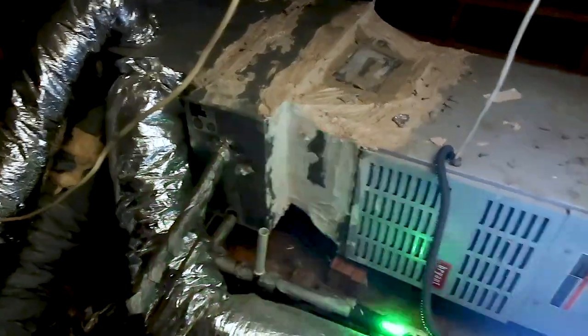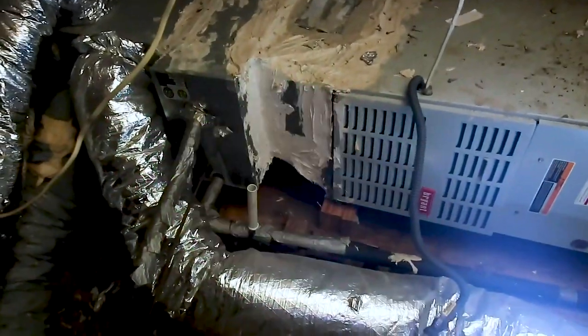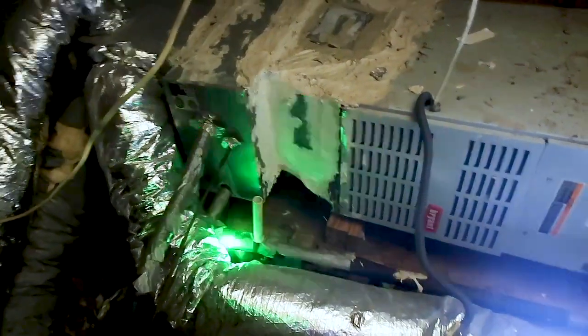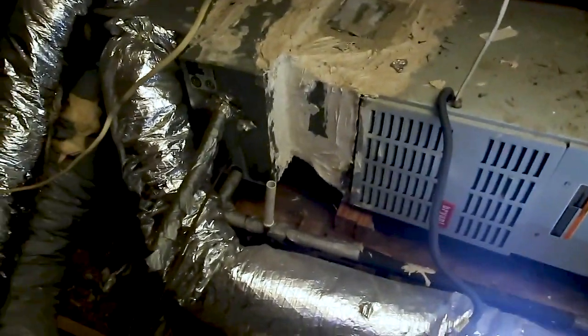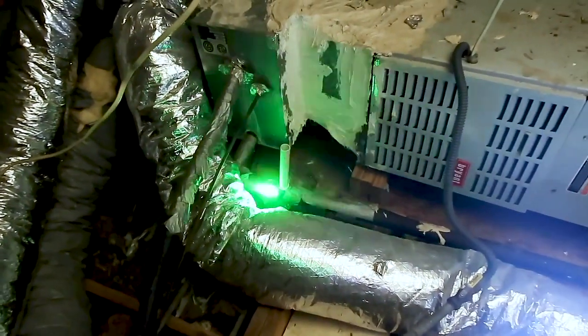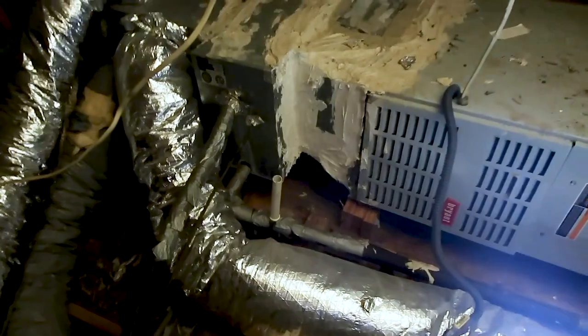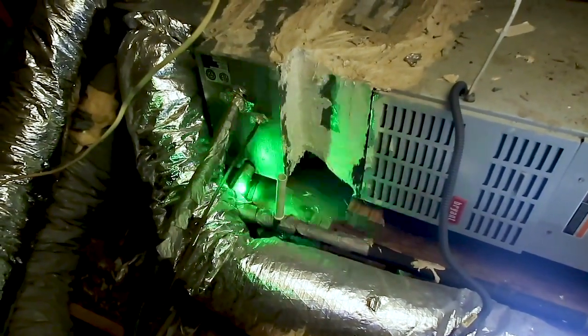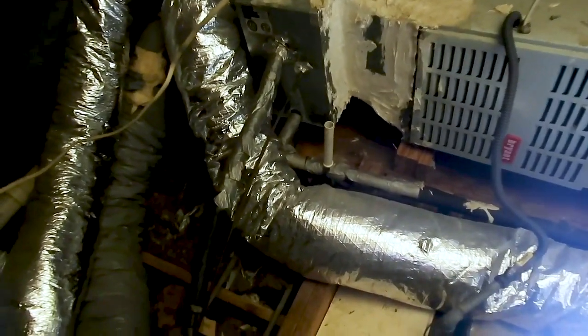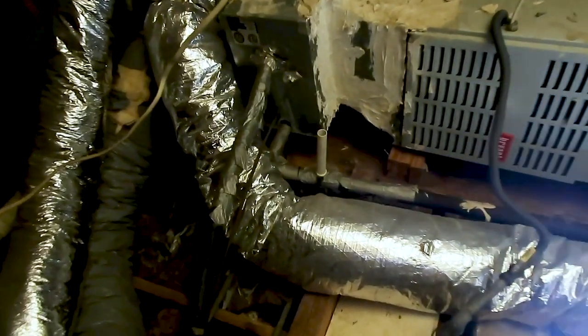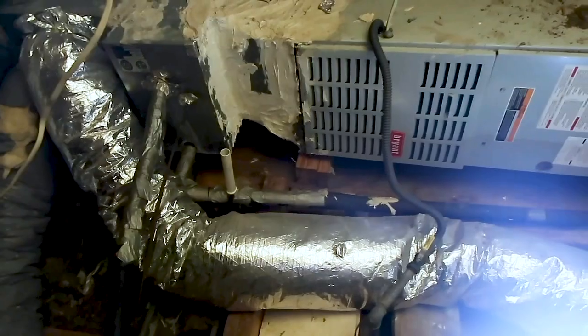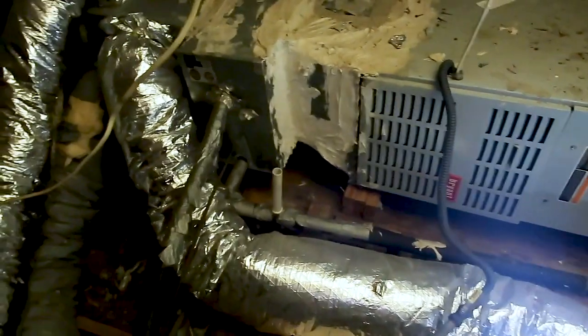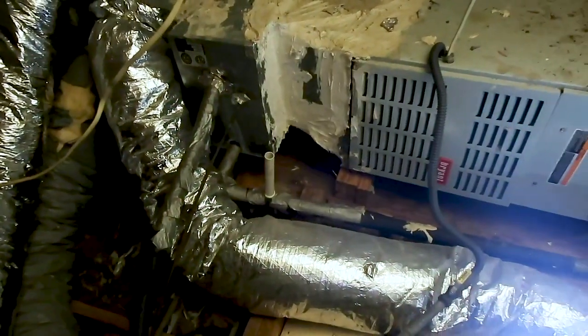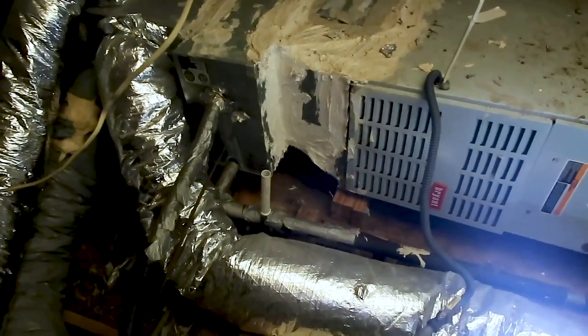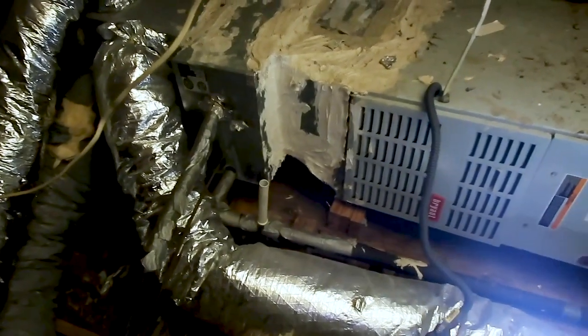Part of looking at your primary drain line is making sure there's a negative slope, since this is a gravity system. You want to see if there's a P-trap in place, and also make sure it's insulated all the way out. I think the code is 5 feet of insulation on the primary drain line, but I live in Houston, Texas, and it's hot, so these condensate all the way through the entire attic system—so I go ahead and call it all out.